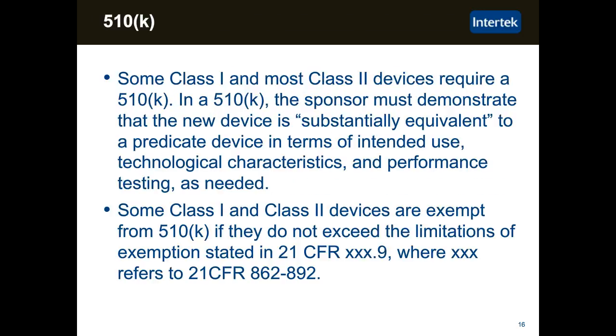Let's talk about the 510K to get started. Some Class 1 and most Class 2 devices will require a 510K. In the 510K, the sponsor must demonstrate that the new device is substantially equivalent to a predicate device in terms of its intended use, the technology that's used in the device, and the performance of the device as demonstrated by testing. Some Class 1 and Class 2 devices are exempt from the 510K if they do not exceed the limitations that are stated in the Code of Federal Regulations for those classes of device.